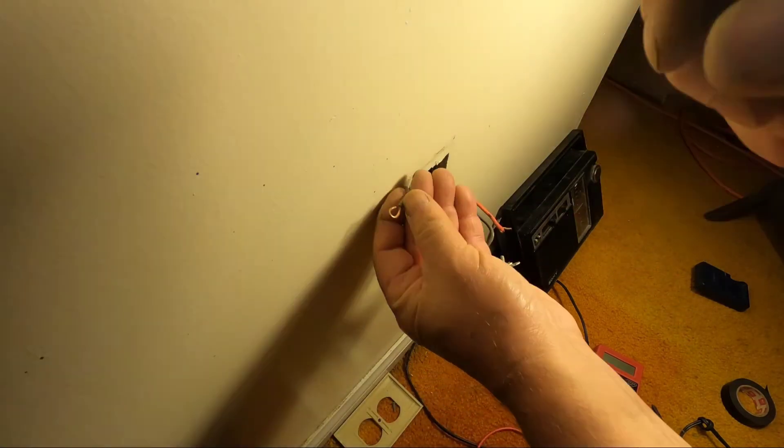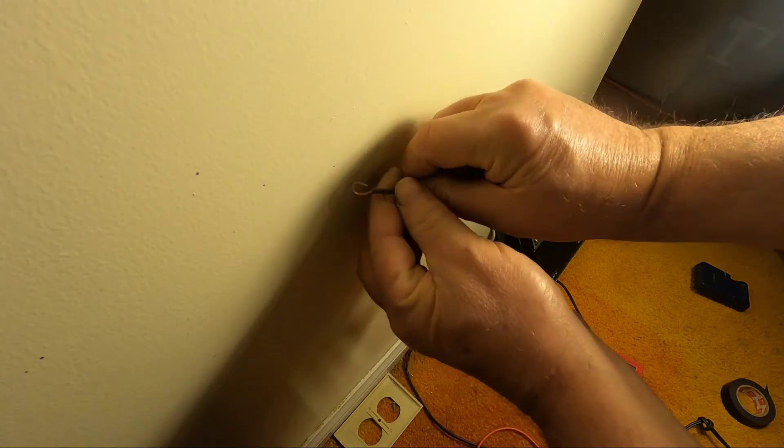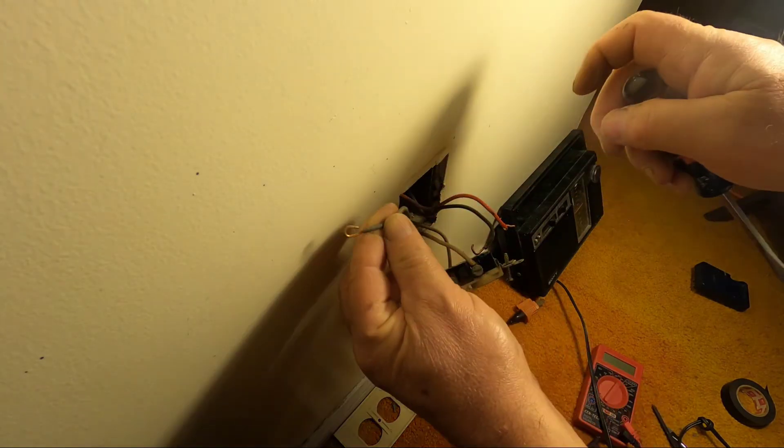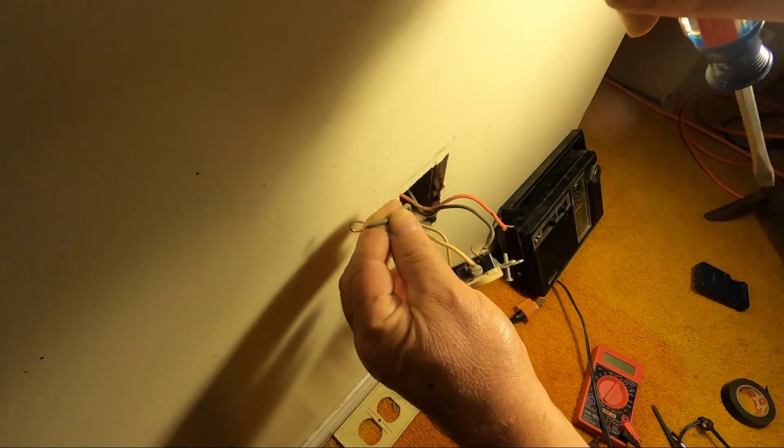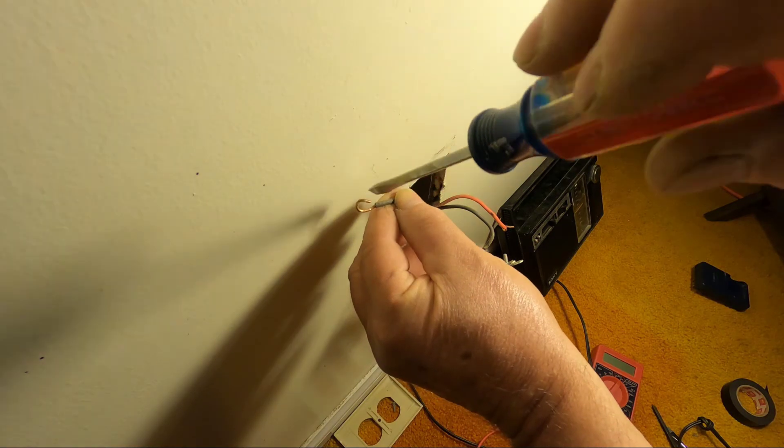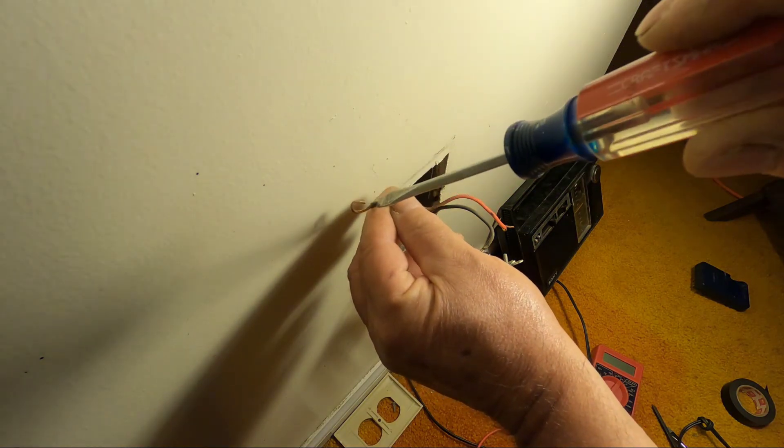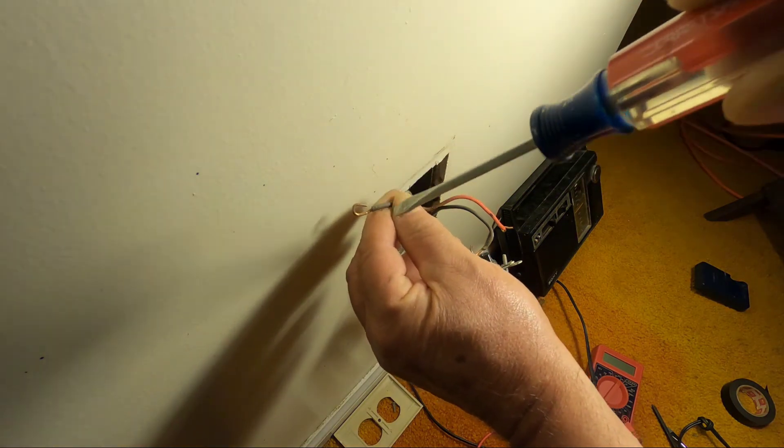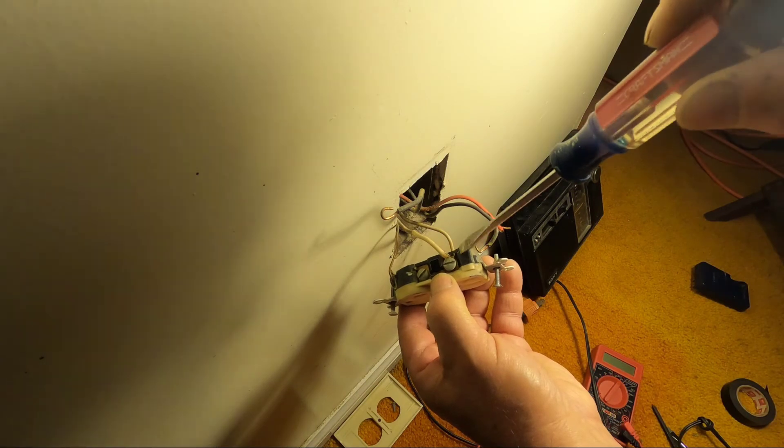Now you notice the way the wire is bent, the loop in the wire. This is important. You want this loop, this opening, I'll point that out again when I put them on. You want this in the direction that the screw is turning, and you don't want the insulation under the screw.